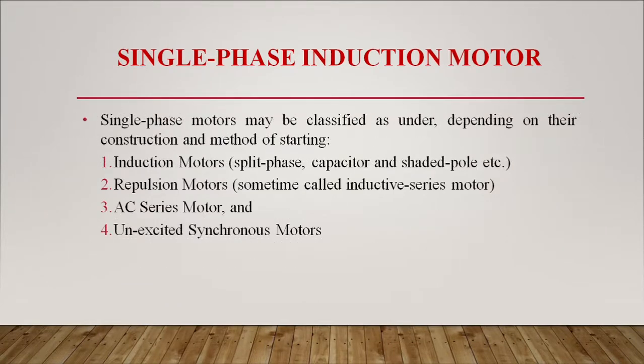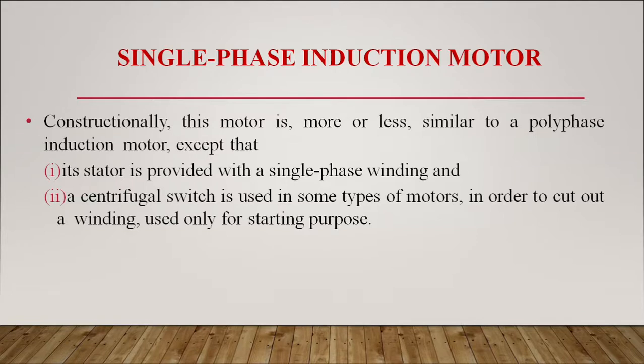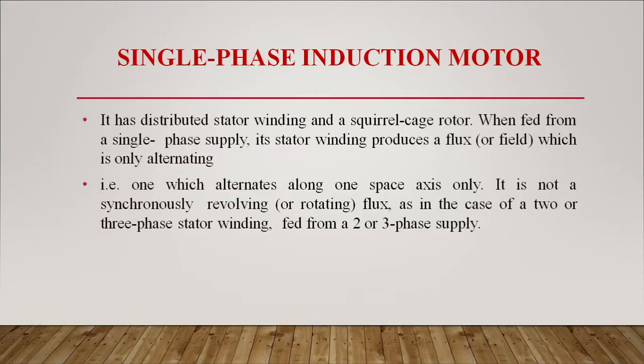Single phase induction motors can be classified based on their construction and method of starting as: induction motors (split phase, capacitor, and shaded pole types), repulsion motors, AC series motors, and unexcited synchronous motors. Constructionally, this motor is similar to a polyphase induction motor except its stator has a single phase winding and a centrifugal switch used to cut out the starting winding. When fed from a single phase supply, the stator winding produces a flux that is only alternating — it alternates along one space axis only, and is not a synchronously revolving flux as in two or three phase motors.